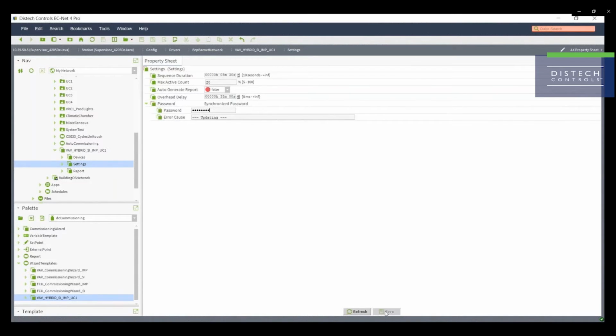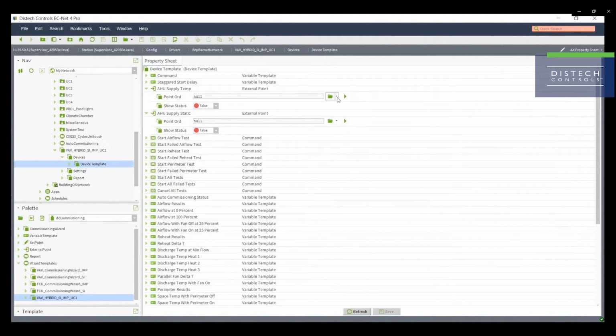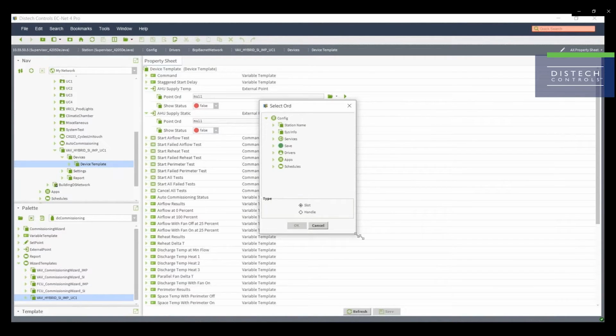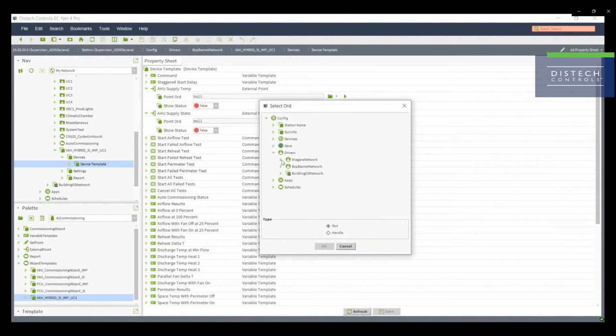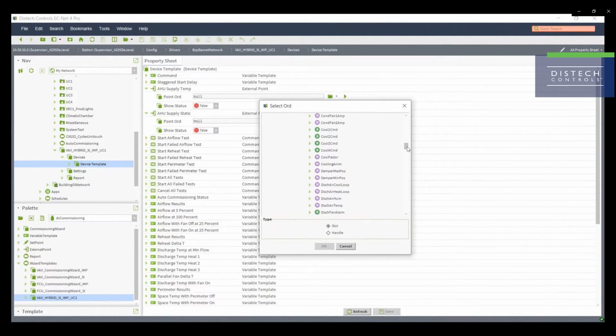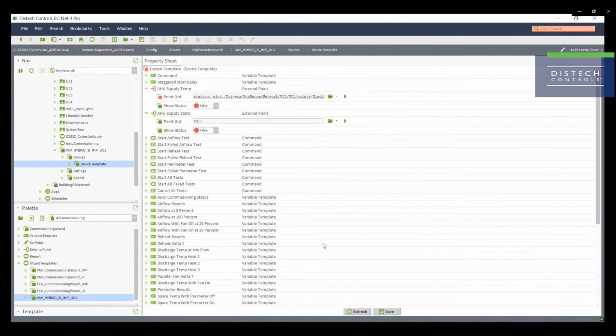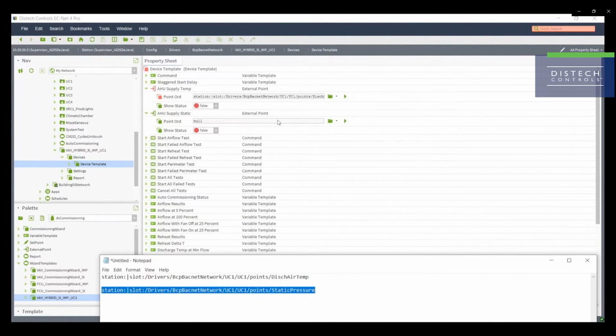This is the same password that is being used in the REST section of the Distech Controls wizard service. Now, let's take a look at the device template property sheet. The commissioning wizard supports logging information from the air handler that is providing air to the VAVs which will be tested. Here, we are going to navigate and link the supply air temperature and the supply air static pressure of the unit that serves the VAVs we wish to test. This adds the support to latch any data inside of ECNet, not just ECLYPSE RESTful information.